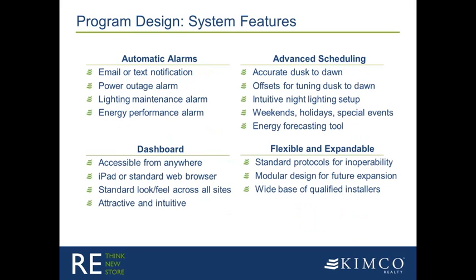I wanted to go over the features of the system we've incorporated. On the top left, alarms — these are received via text or email by our property managers automatically from the system. It keeps them informed of what's going on at their site, including power outages, maintenance requirements, and energy performance. On the top right, the advanced scheduling — this is really the power of the system that drives energy savings. It gives the system very accurate dusk-to-dawn operation rather than relying on a sensor that may get out of calibration, and these times are updated daily.